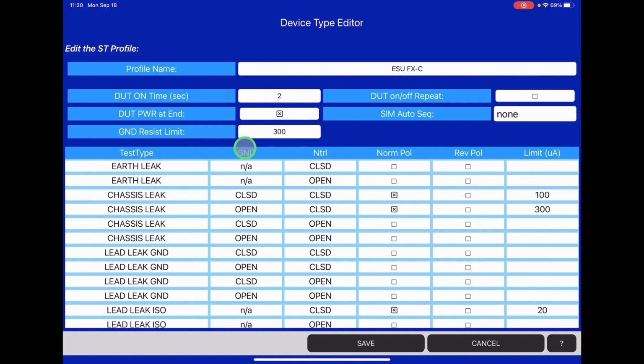And then below here we have the individual tests that are required. So you have the menu on the left of tests that are available. You have the fault condition here in the second column and the third column that you want to go ahead and run. And then you're able to do this in normal polarity or reverse polarity or both. Then you have your program limit. And we need to configure this based on what this Force FXC requires.